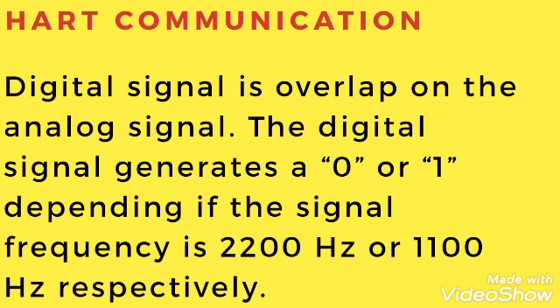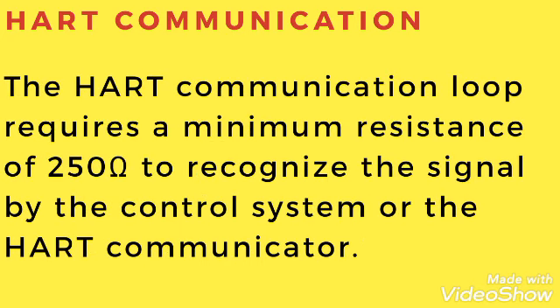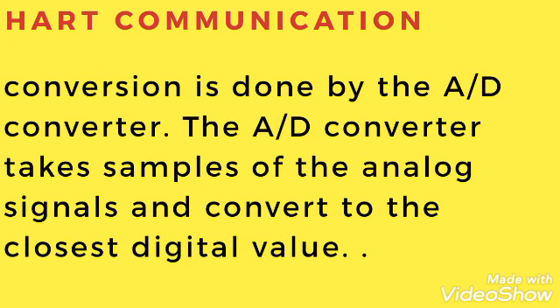HART combines the advantages of the 4-20mA signal but also provides a digital signal with the status of the device. The digital signal is overlapped on the analog signal. The digital signal generates a 0 or 1 depending on whether the signal frequency is 2200Hz or 1200Hz. The HART communication loop requires a minimum resistance of 250 ohms to recognize the signal by the control system.